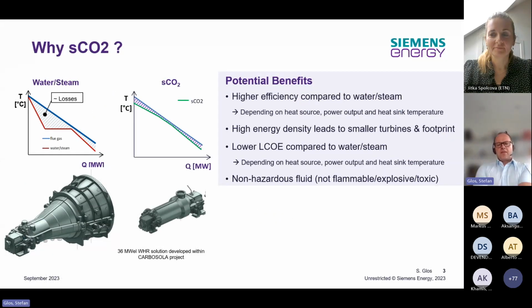So I stopped at the higher efficiency, and I said that this really depends on the use case, on the heat source, on the power output, and especially on the heat sink temperature. The higher fluid density leads to smaller turbines and to a smaller footprint. On the left-hand side, on the lower end, you see a comparison we did once within the CARBOSOLA project, where we investigated a waste heat recovery use case of 36 megawatt and compared a steam turbine on the left-hand side and an sCO2 turbine on the right-hand side. And you see that the main driver for a lower footprint and smaller machines comes from the cold end.